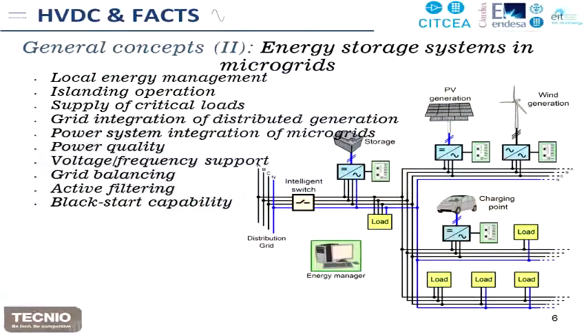Okay, focusing more on energy storage systems, these elements are the ones that give robustness to the system. For example, they allow local energy management if the grid is off, operation as a grid in island mode, and supply of critical loads. When the system is connected to the grid, it can also give special features, such as power quality, voltage and frequency support, grid balancing and active filtering. And in case the grid has an important problem and the system has to restart from zero, it also allows black start capability.